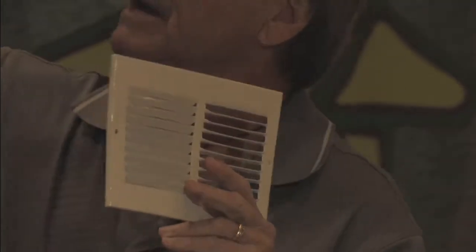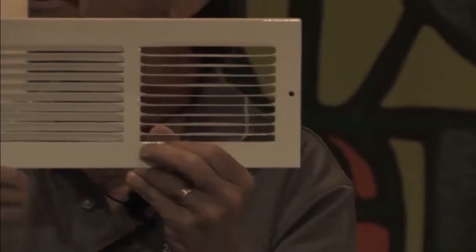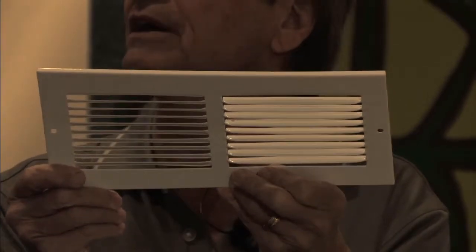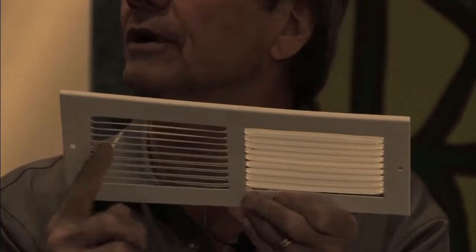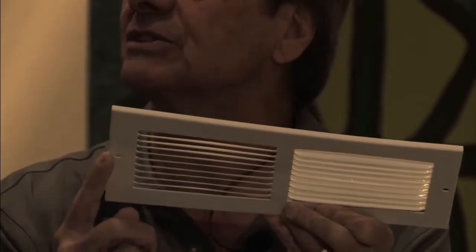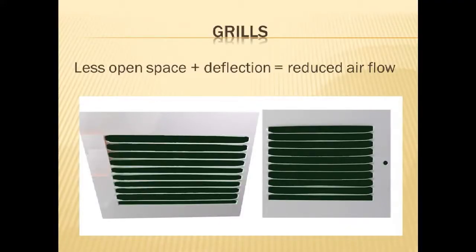If we just bunch this up so we get as good a passage as possible. And what are we getting up on? Okay, so we're down to about 0 on the meter. If I bring my 45-degree ventilator in front of it, we just jumped up a little bit. Okay? And now I put my straight one in front of it. Did it go back down? Yes, it did. You see how it jumps up?